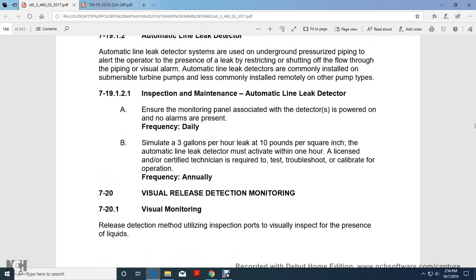Ensure the monitoring panel associated with the detectors is powered on and no alarms are present, daily. Simulate a 3 gallons per hour leak at 10 pounds per square inch; the automatic line leak detector must activate within 1 hour. A licensed and certified technician is required to test, troubleshoot, and calibrate operation, frequency annually.